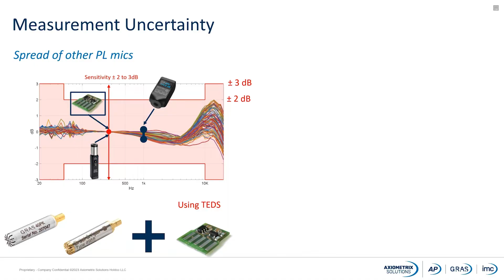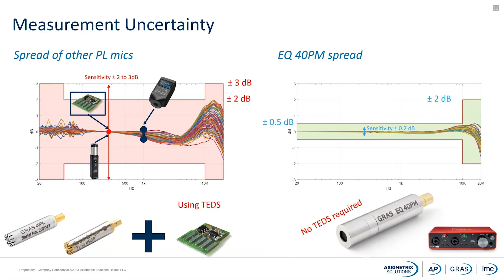Once again, if we compare this with the tolerances in the frequency response and sensitivity of the EQ40PM, we can see that the tolerances are much tighter. And this is why we are not going to require TEDS any longer for calibration if you were doing that, as every microphone is practically the same in terms of sensitivity and also frequency response. Once you adjust your signal chain for one of our GRAS EQ40PM, you can exchange it for another one without the need of making any adjustments.